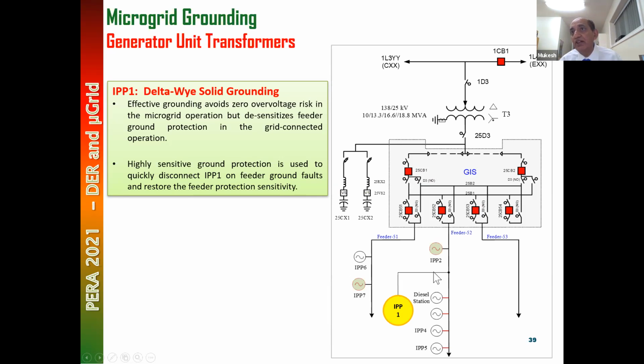Anytime there's a fault here when it is connected, we have put in a very sensitive ground protection for the grid connected mode. If the fault happens anywhere here in grid connected mode, this protection will operate immediately, thereby restoring the sensitivity. So we set highly sensitive ground protection on this for the grid connected mode.